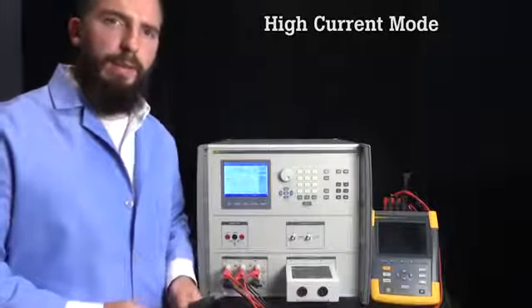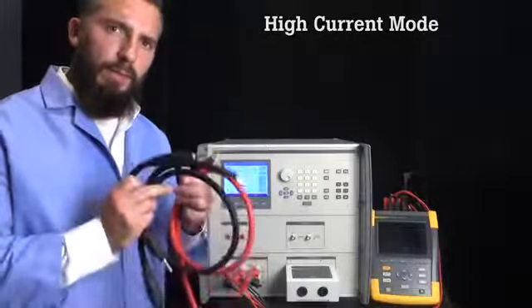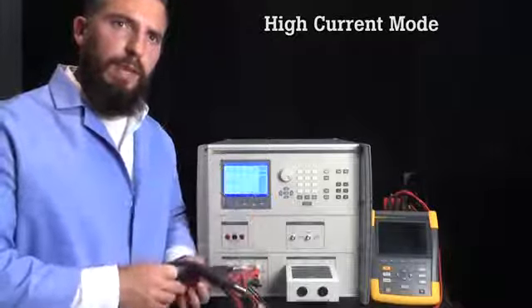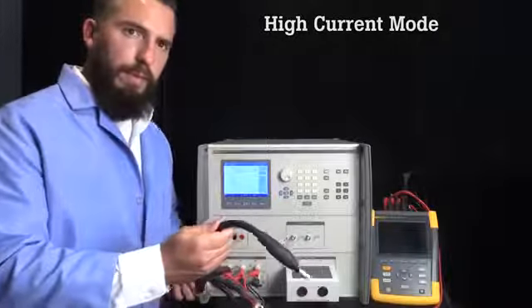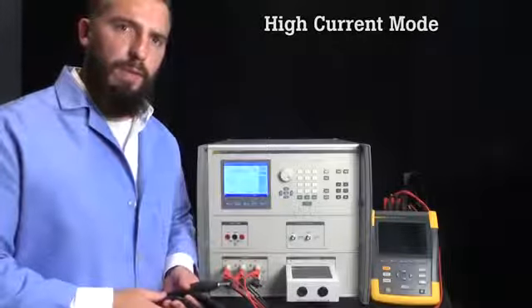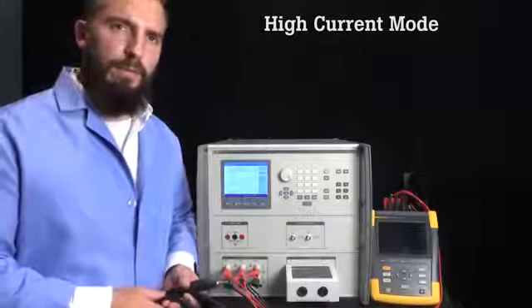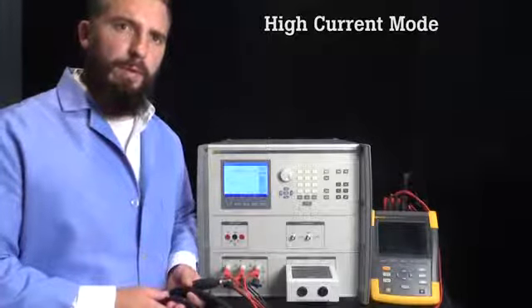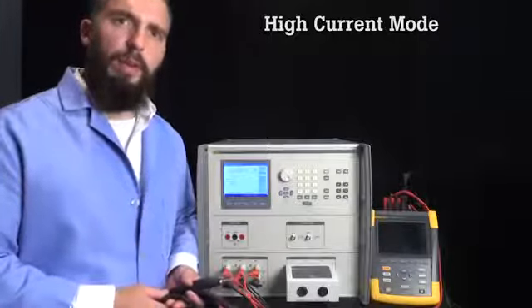The 90 amp high current adapter comes with two high current cables for connecting to the unit under test and the shorting plug. The 90 amp output can be used to drive the 52120A current coils, 25 turns and 50 turns, to simulate a maximum of 4500 amps, useful for calibrating current clamps.